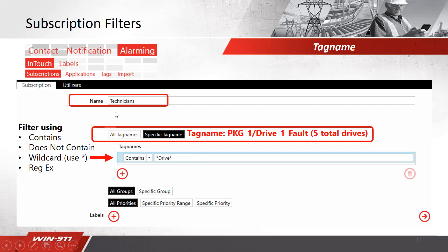Filtering by tag name — the first item was technicians. Name it 'technicians' and filter by specific tag name. We have tag names like pkg1_drive_fault1 with very long names, five items total. You can use the dropdown to select contains, does not contain, or wildcard. I chose 'contains drive', so anything before or after is included. Save that and move on to the next subscription filter.